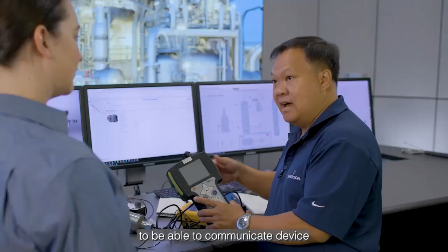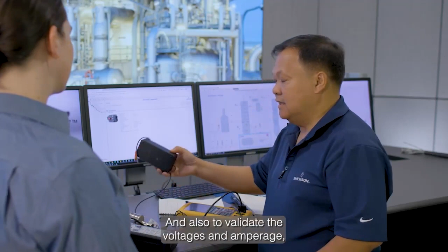At the same time, you need to make some adjustments to your device, so you need a field communicator to communicate with the device and make adjustments as needed. You also need the volt-ohm meters to validate the voltages and amperage. Once you have everything in place and know your route, you need to check out your calibrator and validate that it's in compliance with ISO standards.